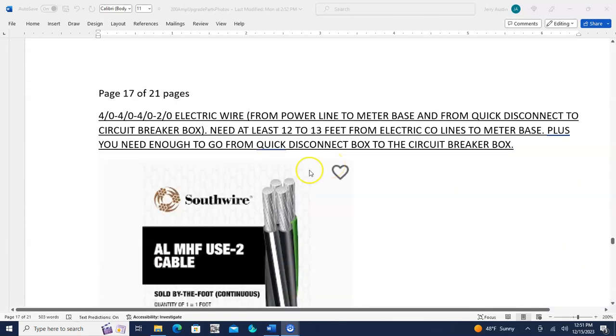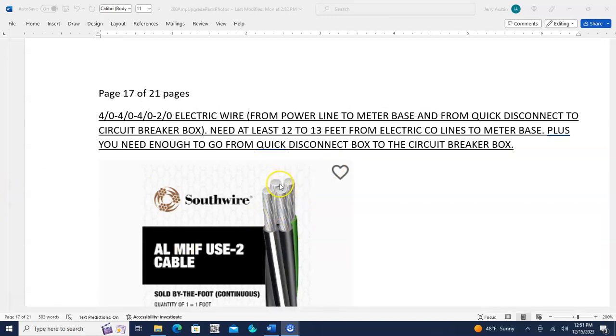This is the cable you need, about $10 a foot. It's got your 3 electric cables, the 2 hot ones right here, and the ground right here, with a white stripe on it. This over here is a safety ground. You don't need that safety ground coming down from the overhead power, you just need these 3 here. But this safety ground is used from the bottom of the meter base into the circuit breaker box.